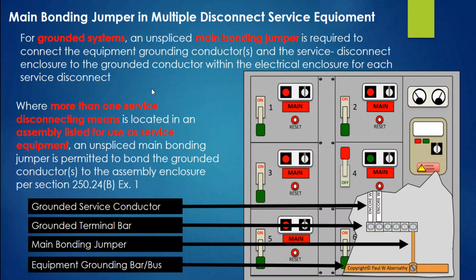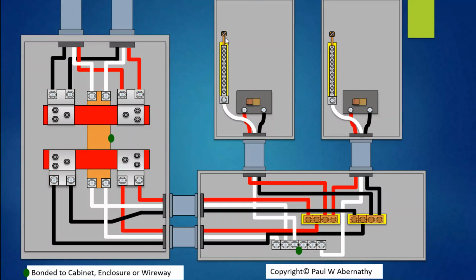All right, let's talk about the main principle of the code. It says the general rule for grounded systems is that an unspliced main bonding jumper is required to connect the equipment grounding conductors and the service disconnect enclosure to the grounded conductor within the electrical enclosure for each service disconnect. Okay, we saw that. And anyway, jumping back, that would be the principle behind this. Whether it's factory supplied or it's a wire, it's making all these connections to the enclosure. And of course, in this location, you might have the grounding electrode conductors going out.